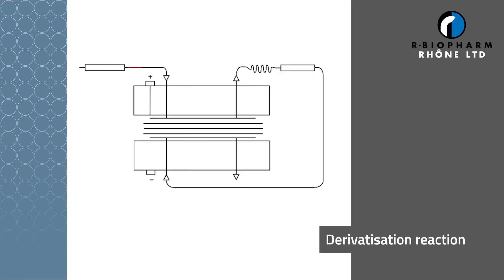The mobile phase and toxin pass through the analytical column and into the Kobra cell. The reaction takes place on the top of the membrane within the Kobra cell, where bromine is generated from the mobile phase. The bromine binds to the aflatoxin molecule, changing the structure and enhancing fluorescence. This then passes through the detector.